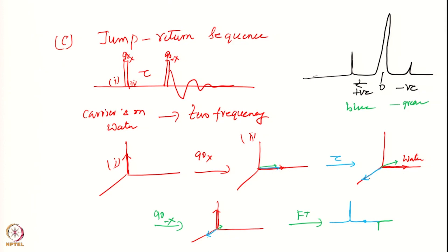The water has gone back to the z-axis and therefore there will be no signal from the water - ideally. In practice, this does not happen ideally and there will be various baseline distortions. Signals which are under the water will also disappear because they too will go back to the z-axis. Therefore, one adjusts tau to get maximum signal for the region of interest.